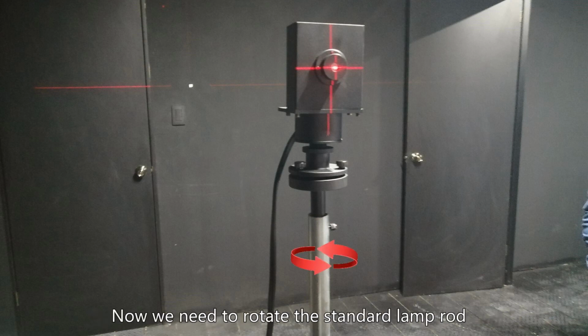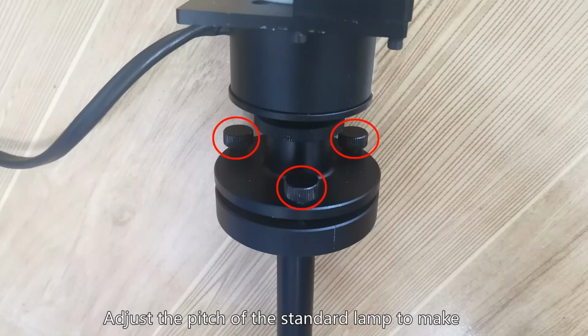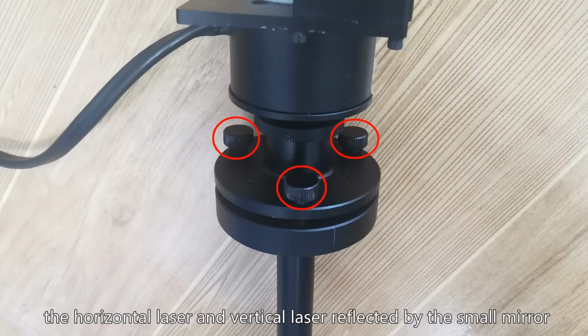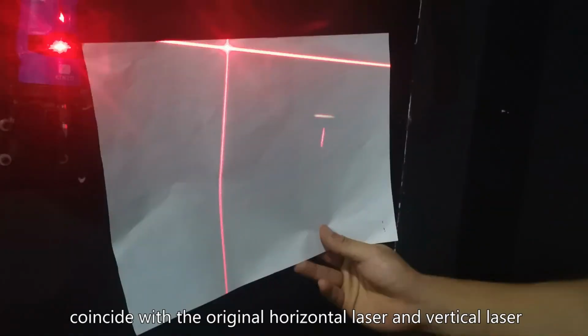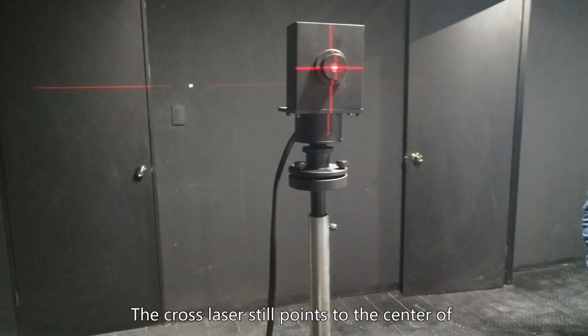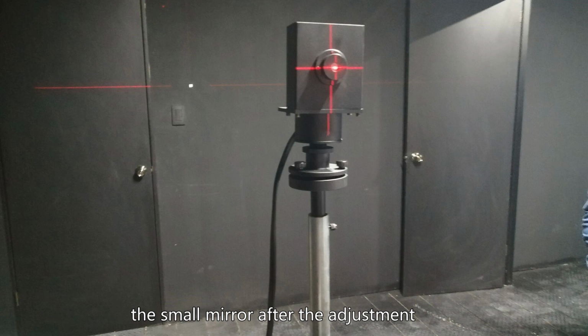Now we need to rotate the standard lamp rod. Adjust the pitch of the standard lamp to make the horizontal laser and vertical laser reflected by the small mirror coincide with the original horizontal laser and vertical laser. The cross laser still points to the center of the small mirror after the adjustment. Otherwise it needs to be adjusted again. This step also requires a lot of patience.